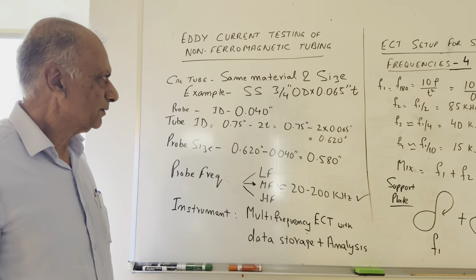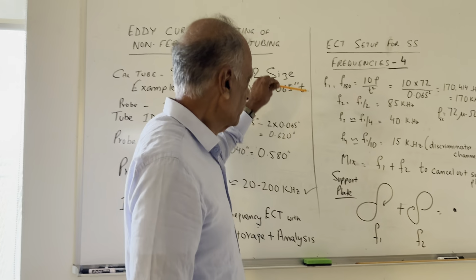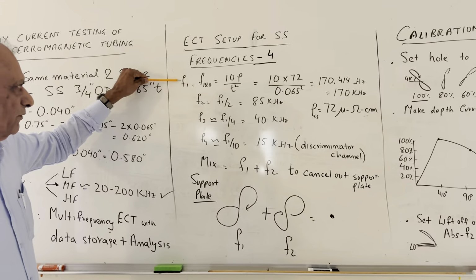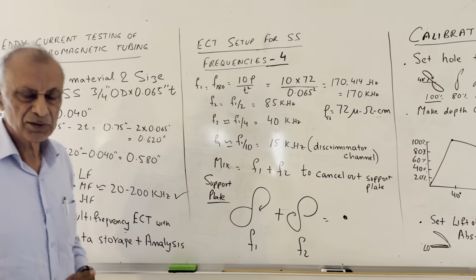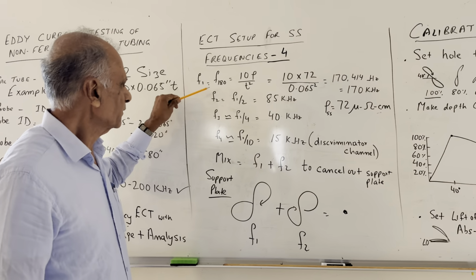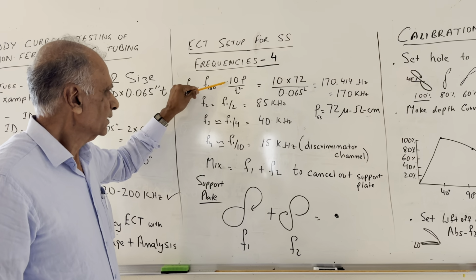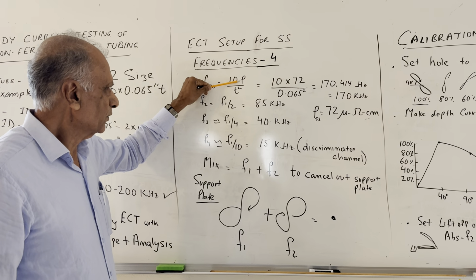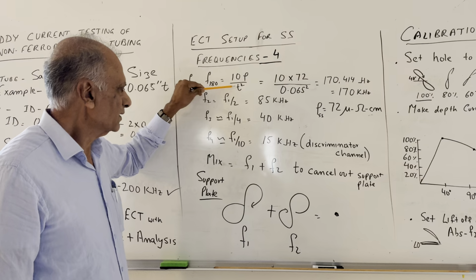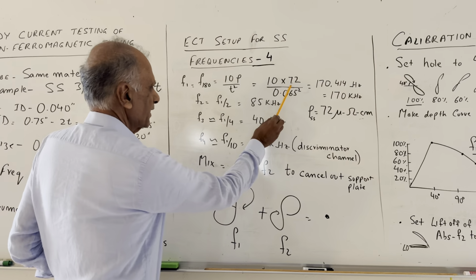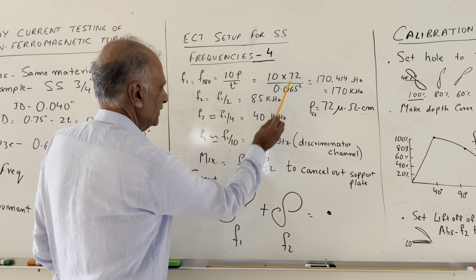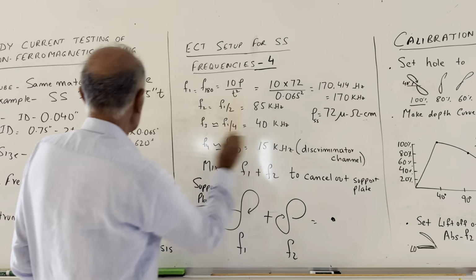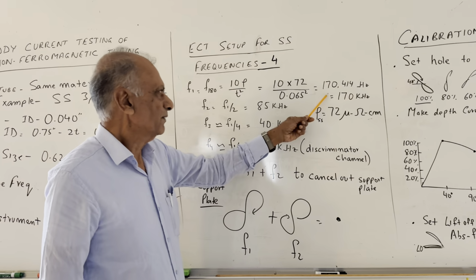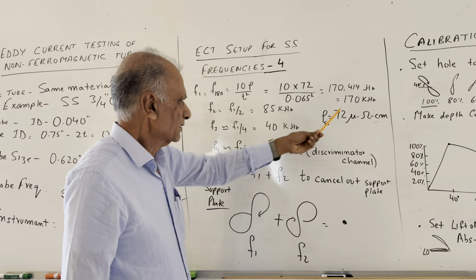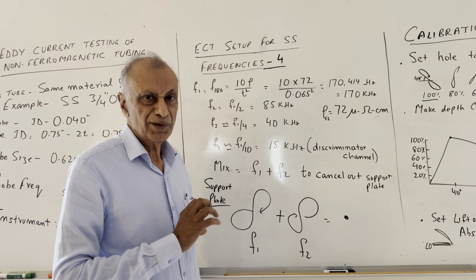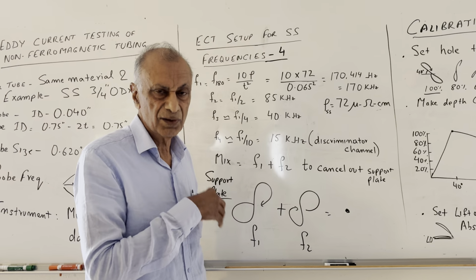Now the next step is to calculate the frequencies for this inspection, and we have to go with 4 frequencies. The prime frequency, which is called F1, is called F180, which produces a phase spread of 180 degrees, and that frequency is 10 rho over T squared, an empirical formula. Rho is the resistivity in micro ohm centimeter, and T is the thickness in inches. So this is 10 times 72 micro ohm centimeter for the stainless steel divided by 0.065 squared, the thickness of the tube, and that comes out to be 170,000 hertz, which is 170 kilohertz. That's my prime frequency, which will produce a phase spread of 180 degrees on those calibration holes.